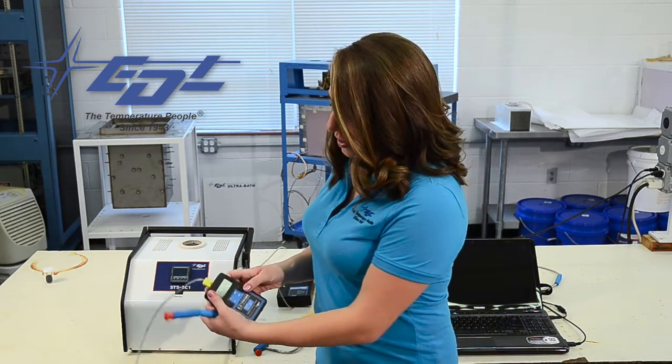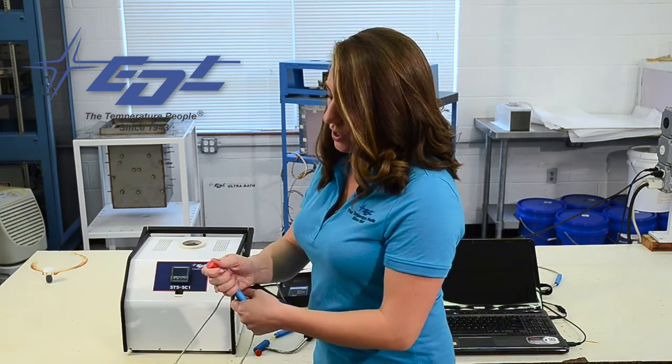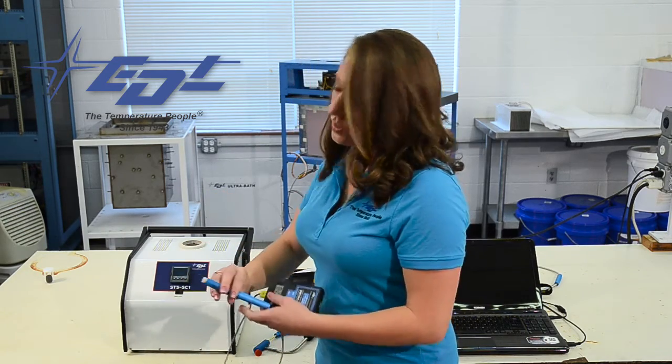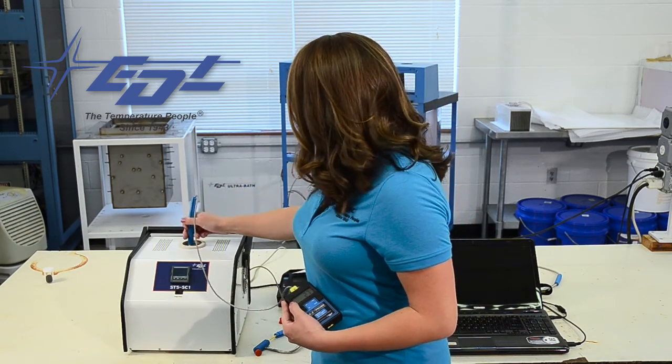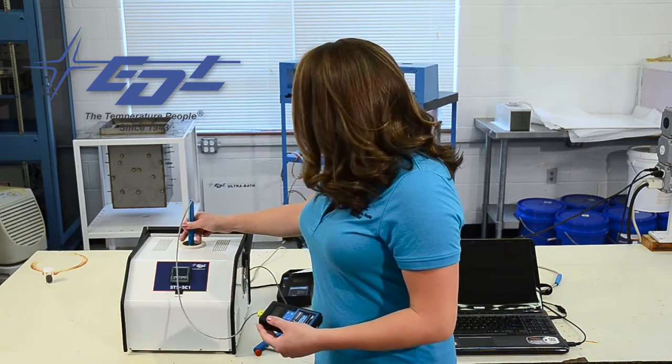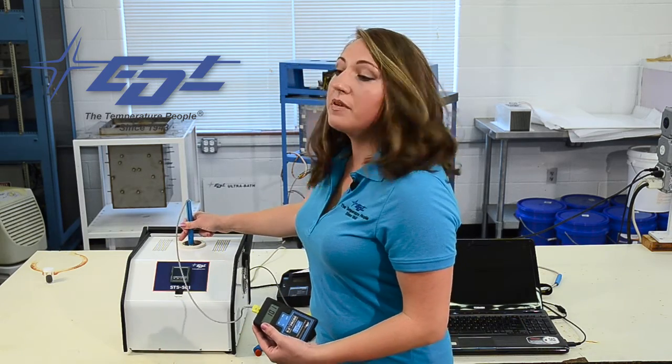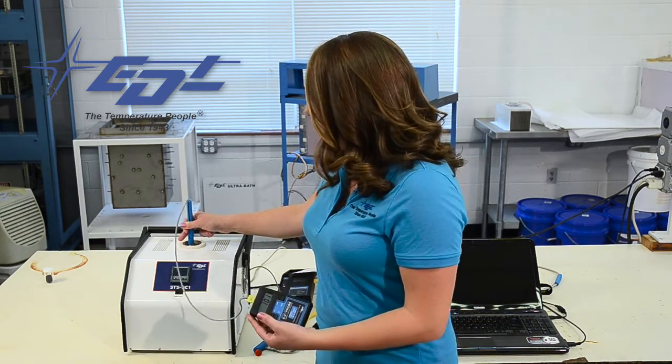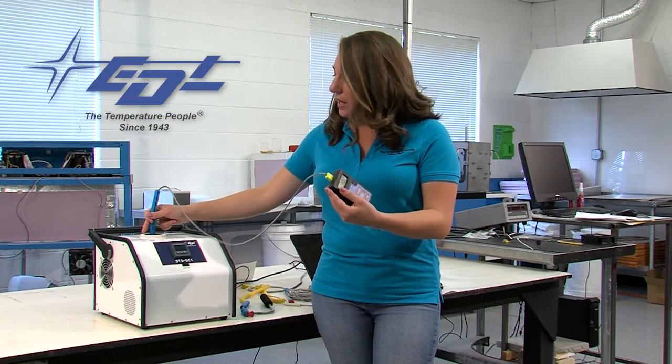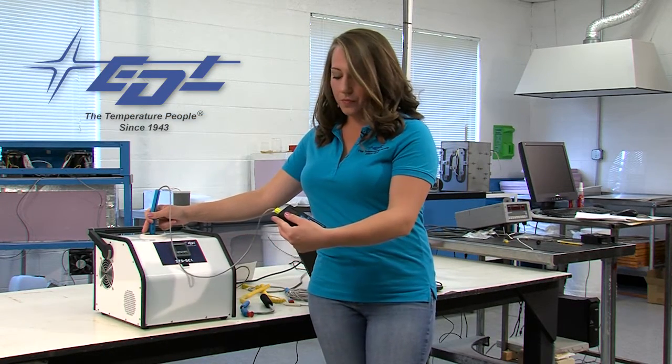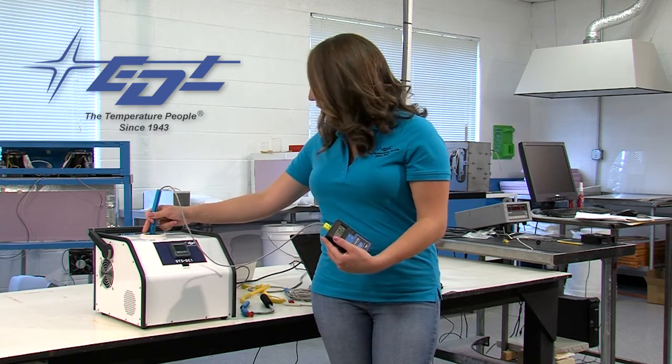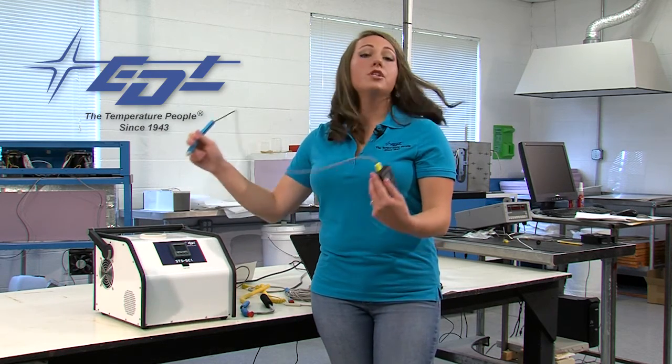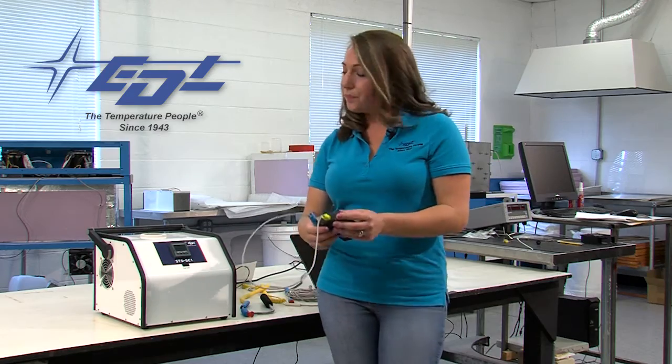You are going to turn your unit under test on. You are going to remove the cap and take your surface sensor. You are just going to hold it onto the block. We are only doing it at 100 degrees Celsius, but be very careful because this may get hot. You are going to hold it on here. Right now it is reading at 102. My unit under test is reading at 102 and our reference is reading at 102. So we know that this unit is ready to go.